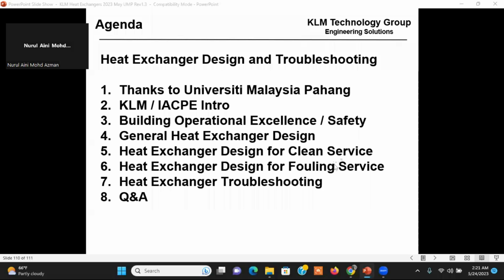What's your experience with ultrasound devices attached to the tube sheet to minimize fouling? That's an excellent question. When you do this UA delta T and you don't have a water flow, you actually have to use ultrasound devices on the water to calculate that water flow. Your heat exchanger vendor needs to come out, and he should do it for free. He should put an ultrasound device on every cooling water flow that you have for your heat exchangers, and tell you how much flow is there. If you don't have enough flow in your heat exchanger, you're going to run into laminar flow. If you run into laminar flow, you're going to have 10 times the fouling that you would have with turbulent flow. So I would have my heat exchanger vendor come out and put ultrasound devices on all of my cooling waters to minimize fouling. Excellent question.